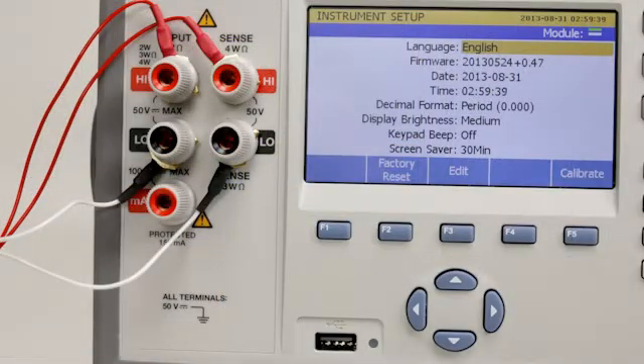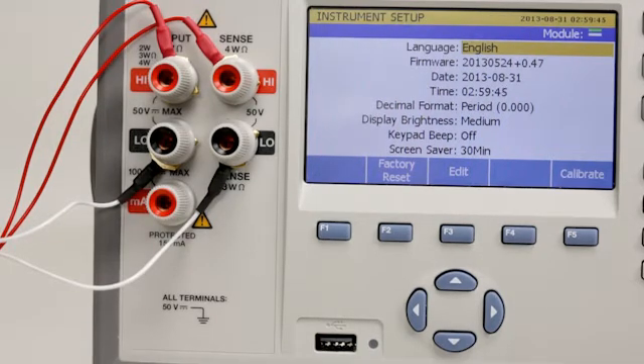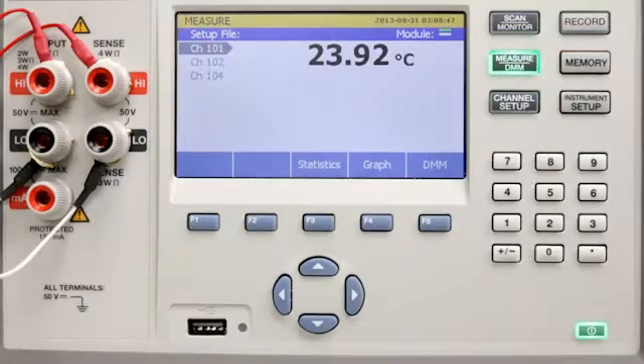Now that we've set up the instrument, suppose we want to use the 1586 in a lab setting to read a PRT. We would first connect the PRT to the five-way binding post. Next, we'll configure the front input channel to read a PRT.